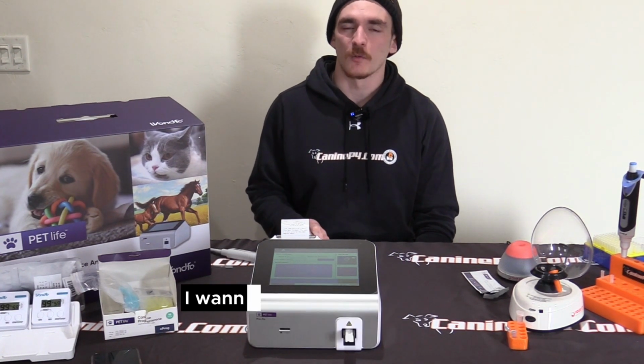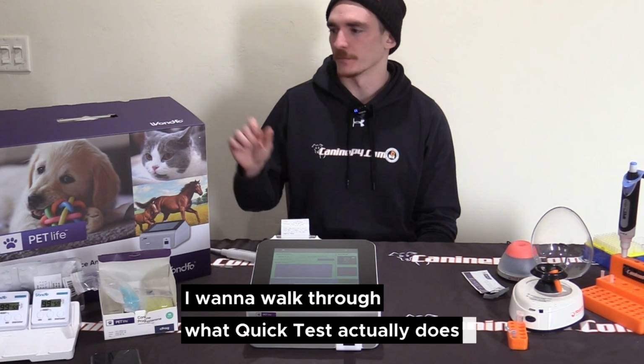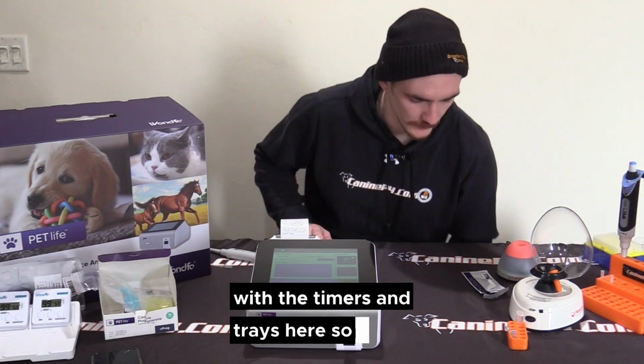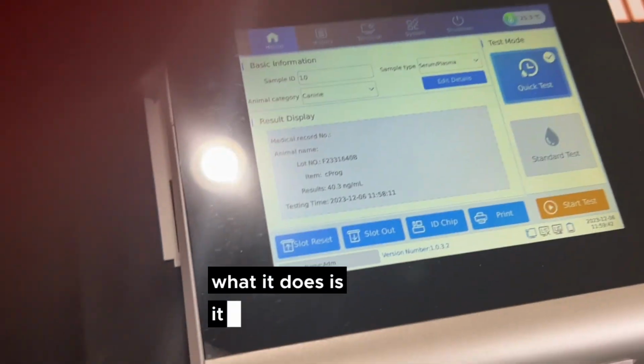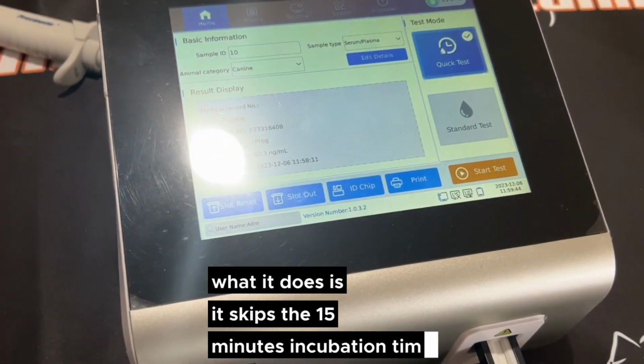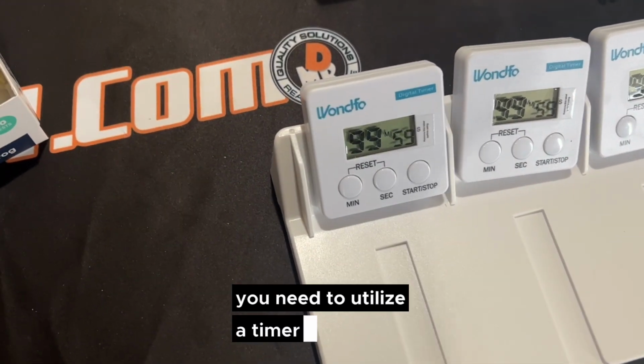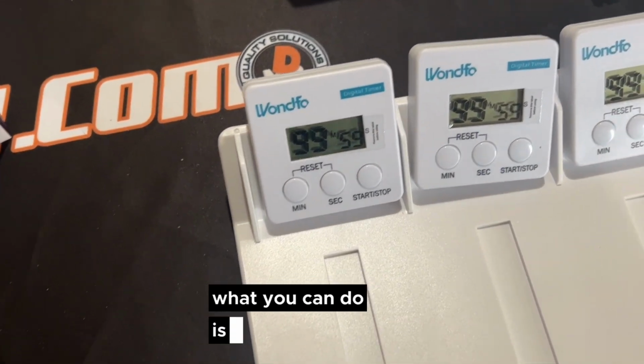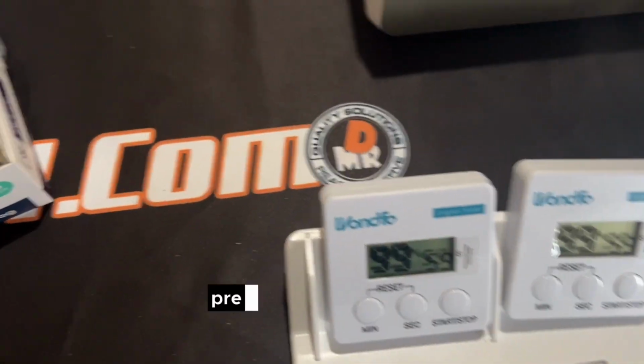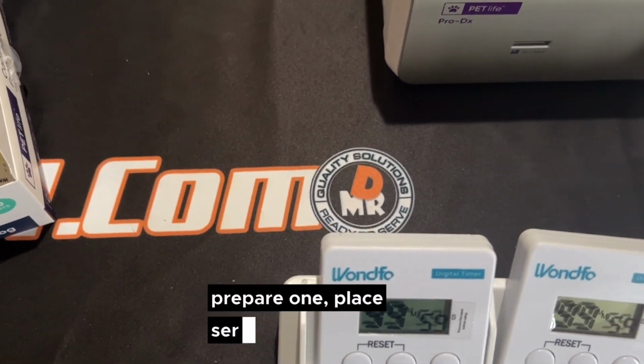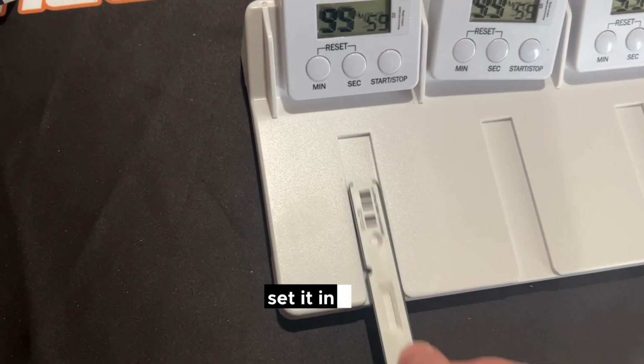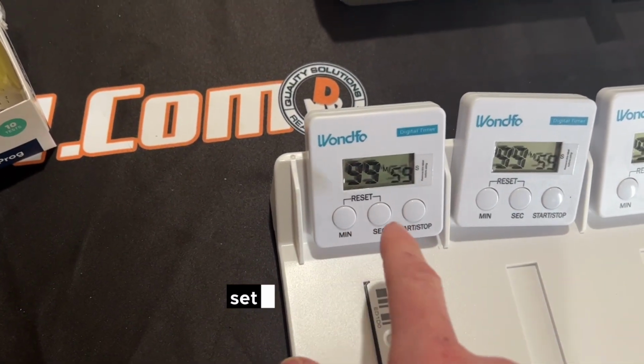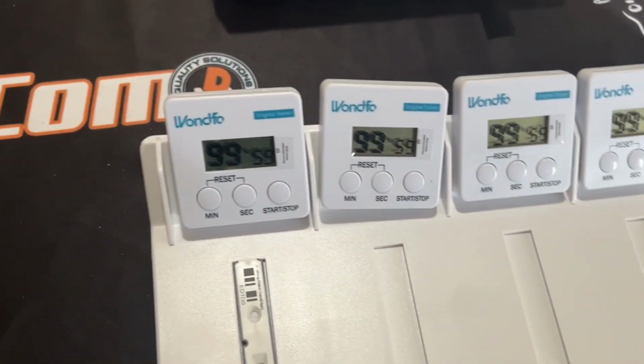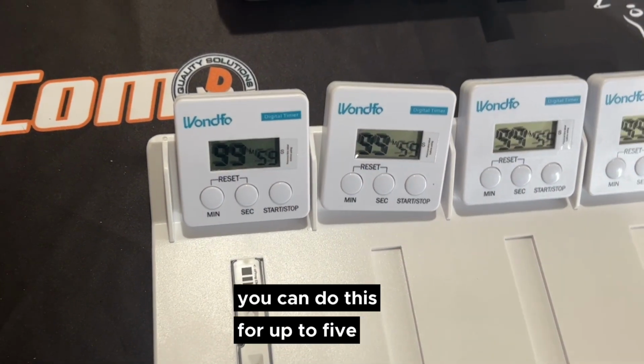First, I want to walk through what quick test actually does with the timers and trays here. So, when you select quick test on the machine, what it does is it skips the 15 minutes of incubation time. So if you're going to use quick test, you need to utilize a timer set like this. What you can do is prepare your samples, prepare one, place the serum into the cartridge, set it into the slot like this, set timer 15 minutes, and start it. You can do this for up to 5 tests.